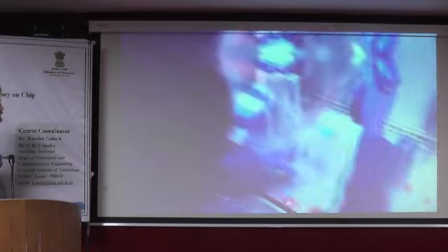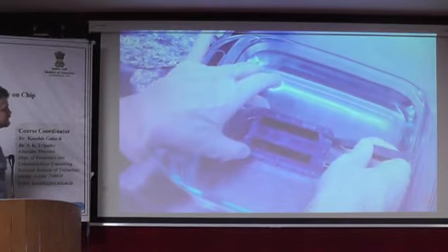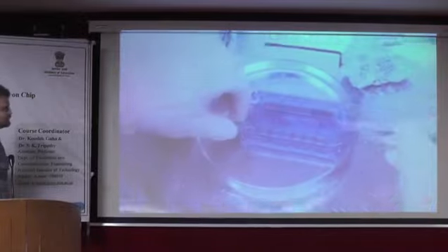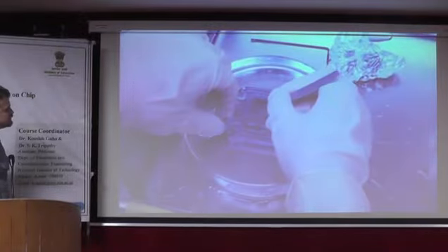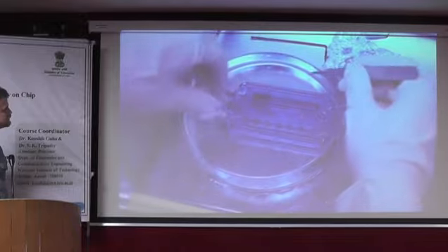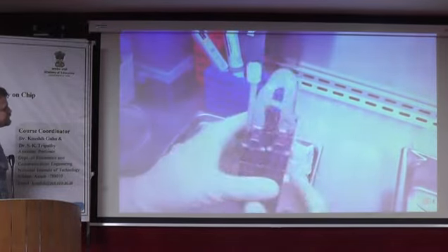Tissue culture protocols have also been optimized to reproducibly grow renal tubule cells and maintain their function. The silicon membranes were mounted in polycarbonate housing to construct hemofilters, and in similar fashion, bioreactors were assembled to immunoprotect the renal tubule cells.